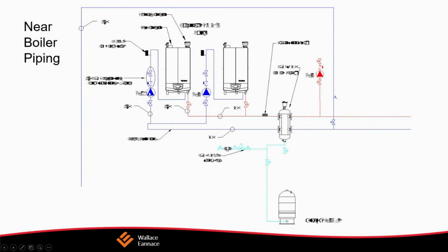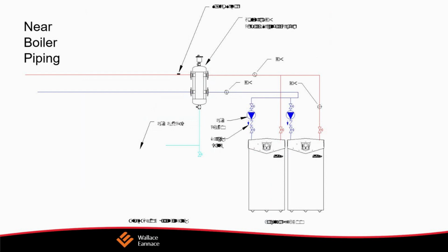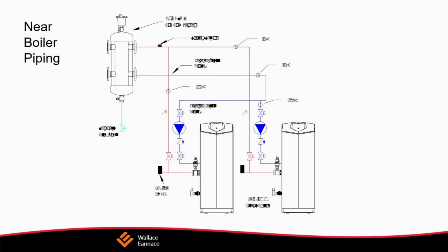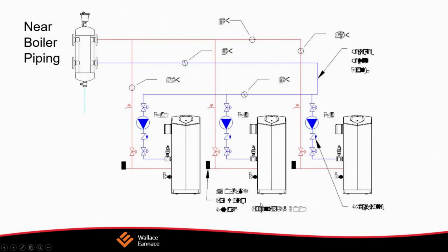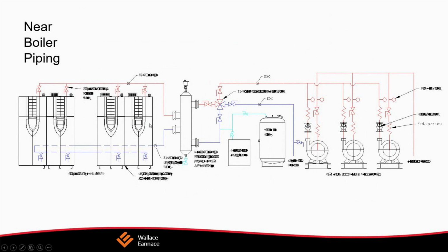Here we see a larger building with a custom primary secondary header, and we go into a 4-way mixing valve for temperature control, connected to a series of pumps, once again also pumping away from the expansion tank. Here we have another primary secondary header connected with a simple installation. Again, the expansion tank is connected to the bottom, and we pump away. Notice that we pump away on the return side from the expansion tank. And also here we have a 3-way mixing valve going to zone valves, very simple, and also going direct, say, to a larger zone, maybe an air handler or something along those lines.